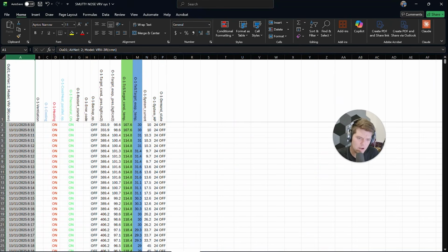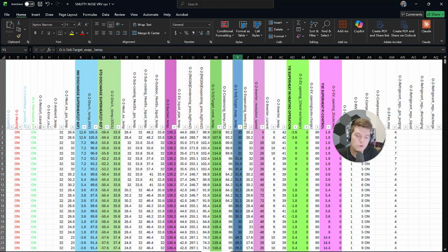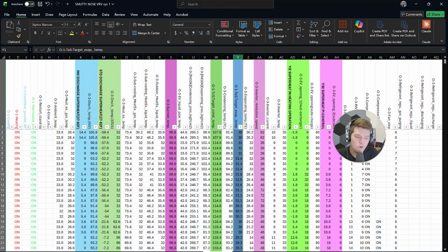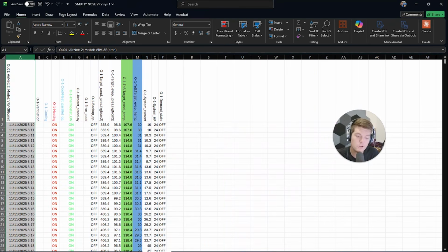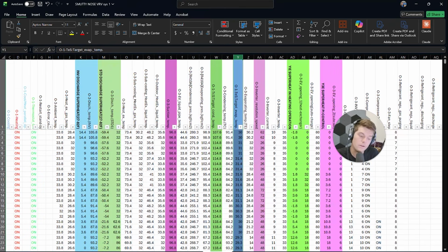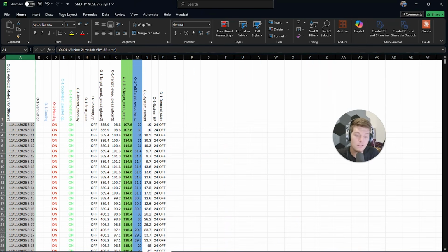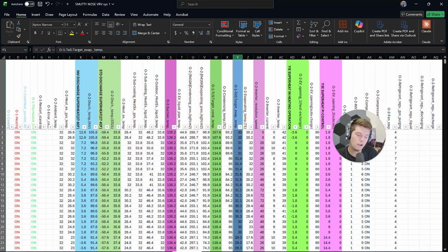Well, I would go in here and say, okay, OU1 should always be targets. OU2 should be the first module. OU3 should also be the second module, right? This is targets from Service Checker, OU1, OU2. Now, they're obviously named different things, but this is how it should be in this order. If you go to this tab and you see that this is an outdoor unit and this is your targets, well, then the files were labeled incorrectly when they were exported.